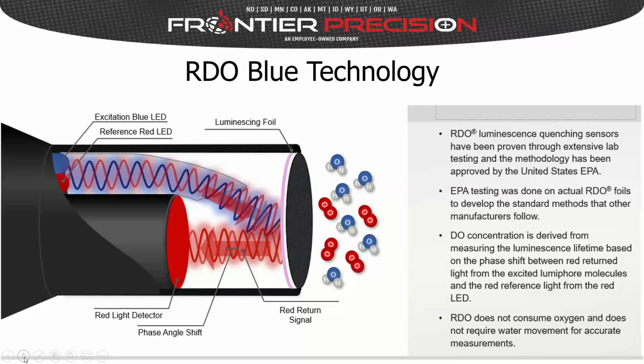If we were to do a cutaway of the sensor and describe what's going on with this, basically you have two LEDs, a blue and a red LED, that shine onto the back side of this luminescing foil. And depending on the amount of dissolved oxygen that's present on the outside of this, you get a red return signal, and we're essentially looking at this phase shift that occurs in the return signal as opposed to the reference LED, and the phase angle shift basically gives you a very precise indication of the amount of dissolved oxygen that's present on this luminescing foil.